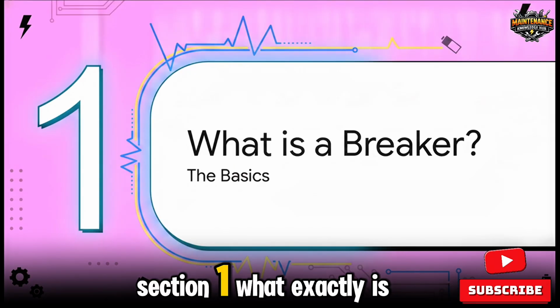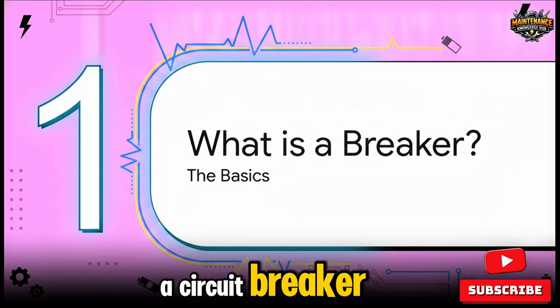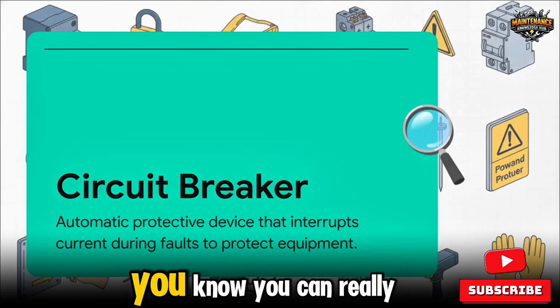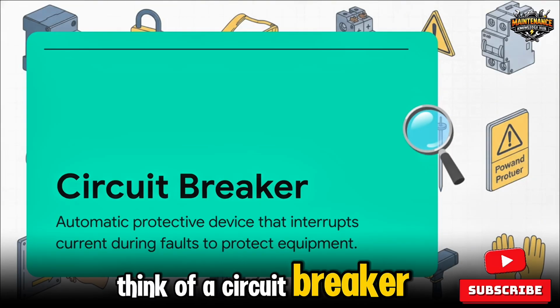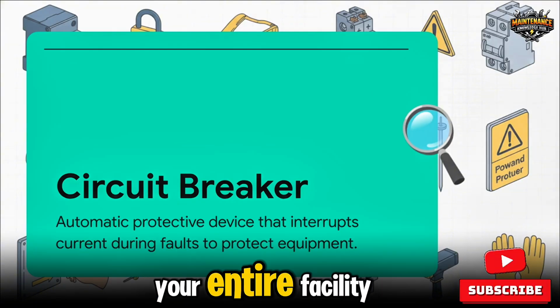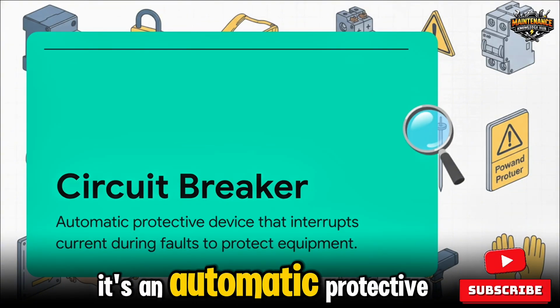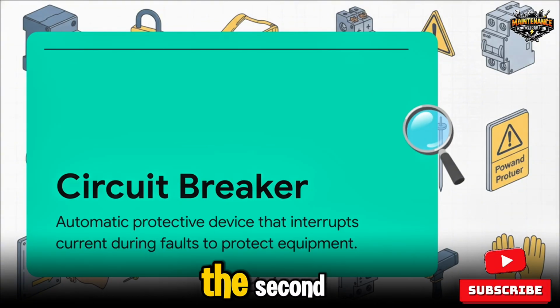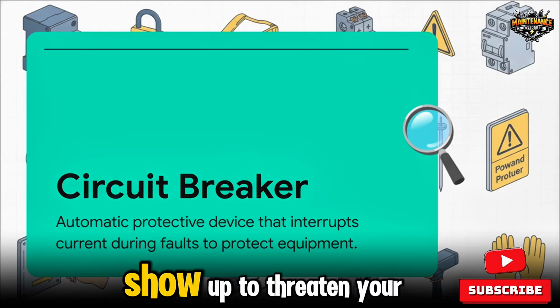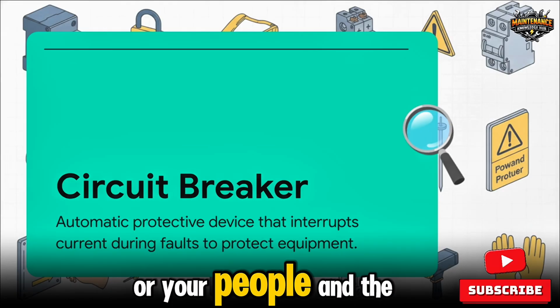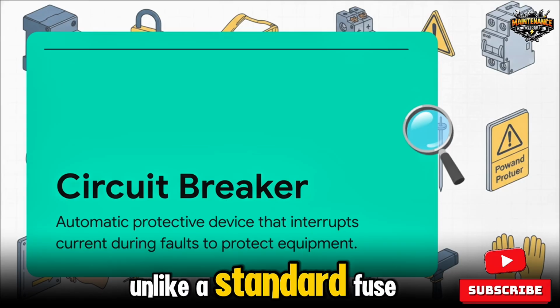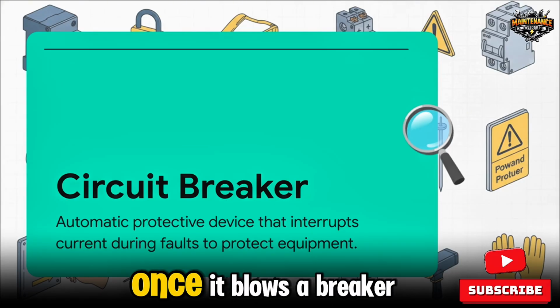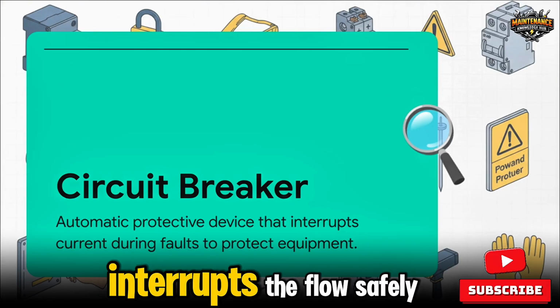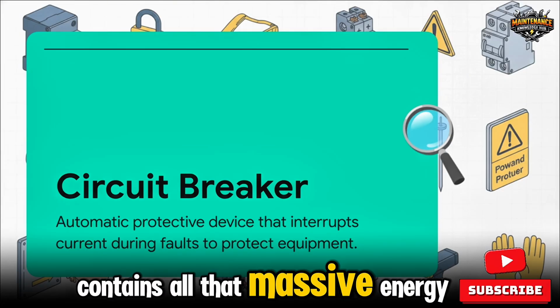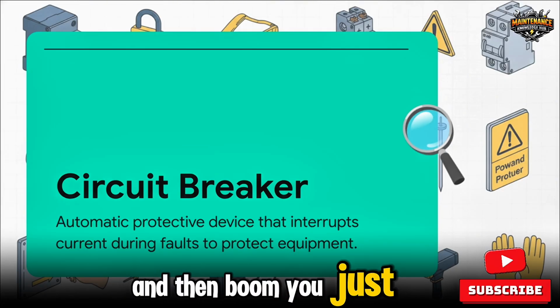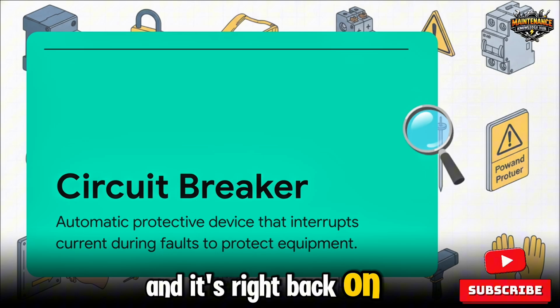All right, Section 1. What exactly is a circuit breaker? Just covering the basics here. You can really think of a circuit breaker as the invisible bouncer of your entire facility. It's an automatic protective switching device that steps in the second dangerous electrical conditions show up to threaten your equipment or your people. And the real beauty of it, unlike a standard fuse that you have to toss out and replace once it blows, a breaker interrupts the flow, safely contains all that massive energy, and then boom, you just mechanically reset it and it's right back on duty.